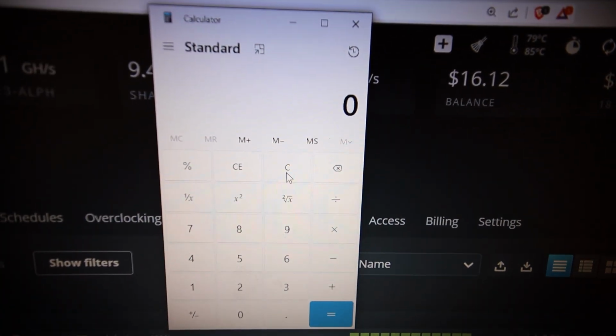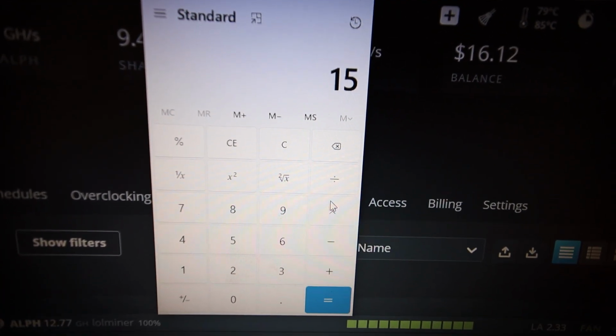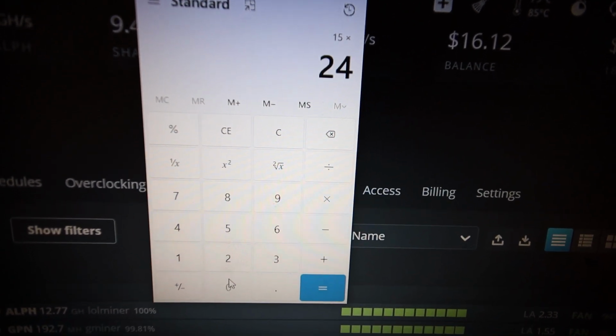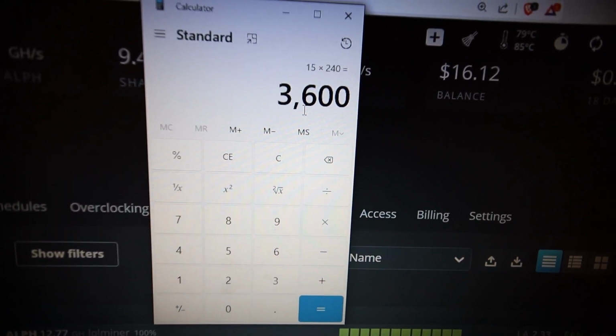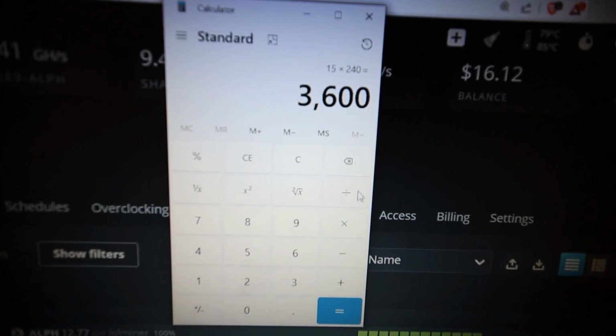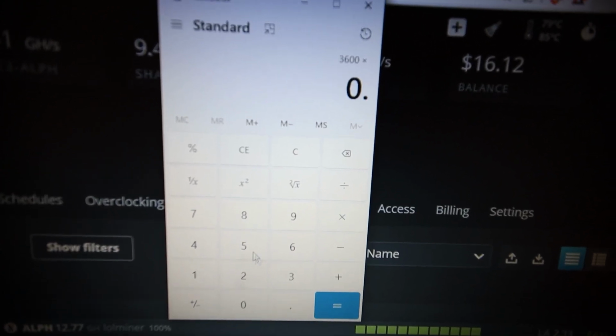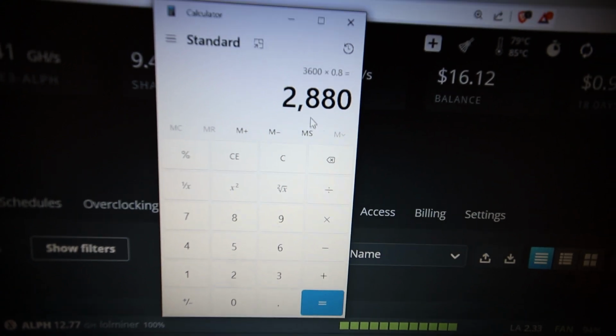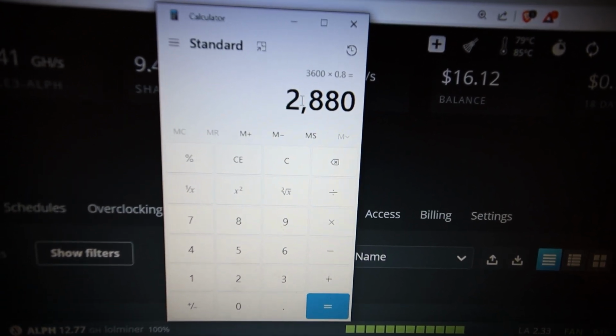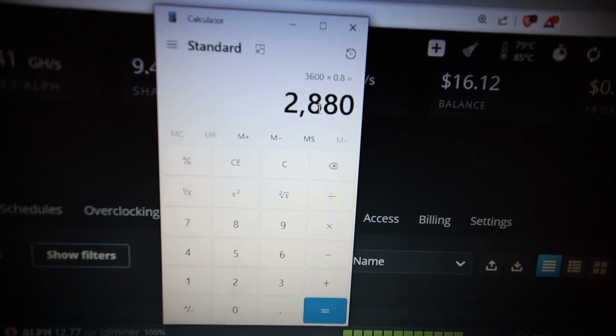Okay, so if I do some quick math here: 15 amps times 240 volts, just going by one of the banks on the Tripp Lite, that'd be about 3,600 watts. Now if I times this by 0.8 for the 80% rule, then the max I should really go on that bank is 2,900 watts.